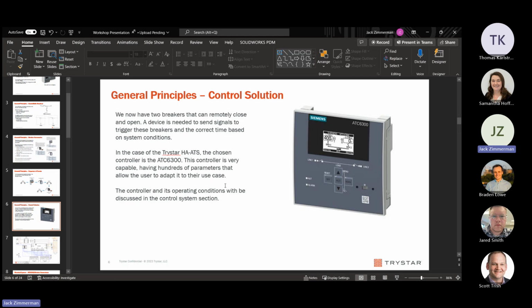We're setting it up before we send it out, per the nominal voltage, nominal frequency, the standards that we know are going to be involved with the job. Specialty functionality is more of a question - I've had this discussion before about how deep we want to go in programming this for the customer. If we commission it, we probably go all the way through, but for the most part it's just making it an automatic transfer switch that works for the conditions set in the quote. Then we deliver the manual for the ATC controller along with it, and if they want to do something extra, they're more than happy to.